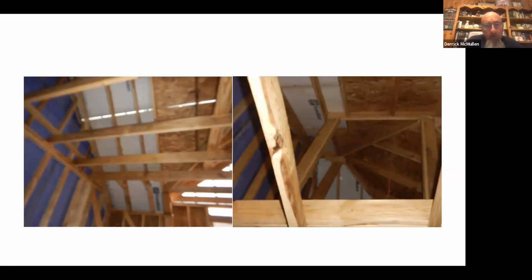You can use, there's different materials also. This just happens to be the one that I had pictures of. I was actually driving through the Woodlands and I saw this purple material and I thought, what in the world is that? So I actually turned around, went over there and went through this house and just took pictures of it. Because this was actually a 2-family dwelling, but they put fire separation in as a townhome for some reason. I don't know if the engineer did that specifically or didn't know what they were doing or what, but they over-engineered this fire separation on this 2-family dwelling. But at any rate, that's when you would need the fire separation in the roof.